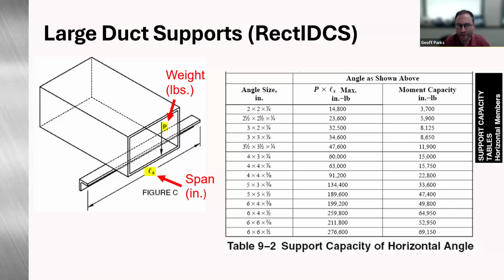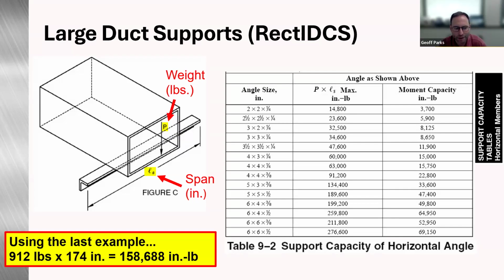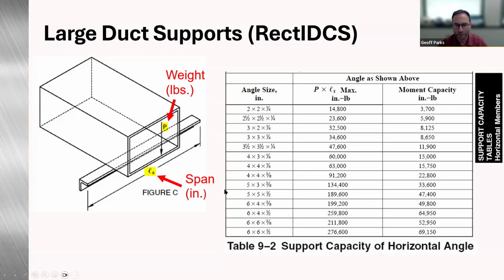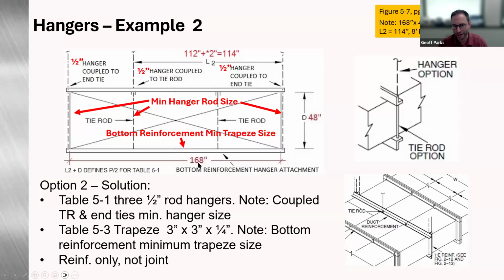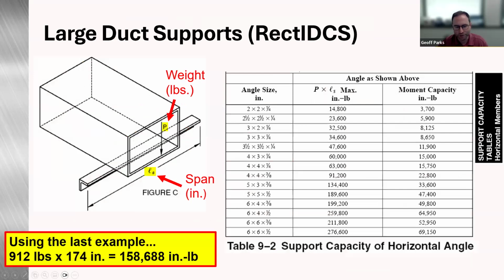So if we were to size this out of the rectangular duct construction standards, so this is table 9-2. I'm just trying to show an example of what that angle would be. So if we used the last example and we said, hey, we have 912 pounds times 174, that would have been our full span. So our full span would have been 168 plus 3 and 3, which would have given us the 174 inches. So we multiply those together and we get 158,688.